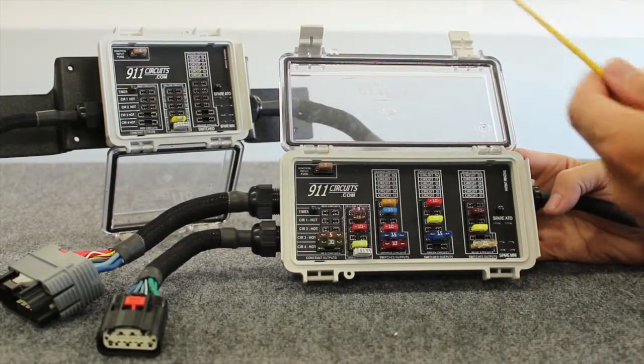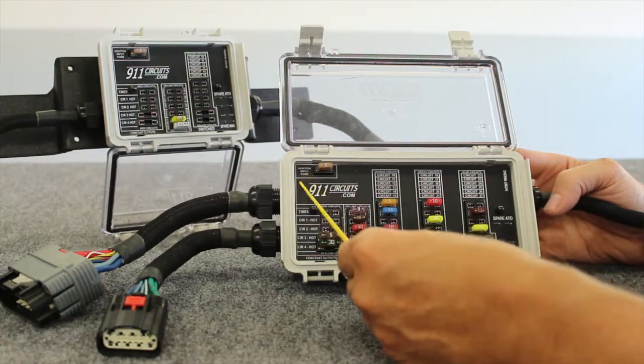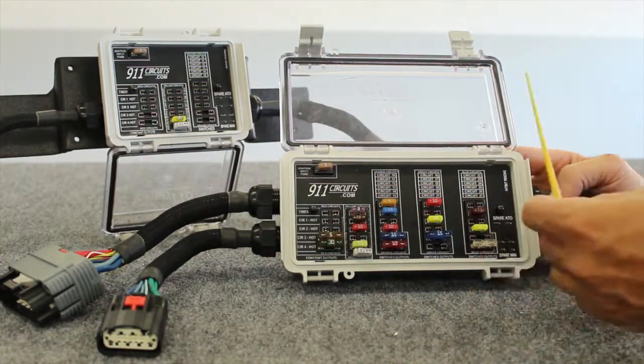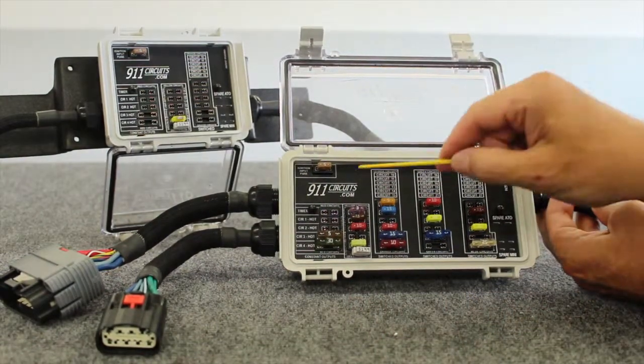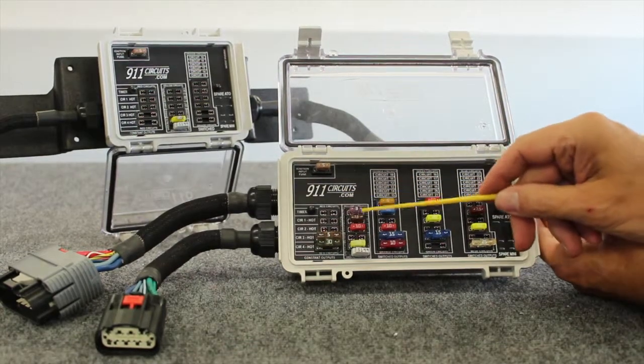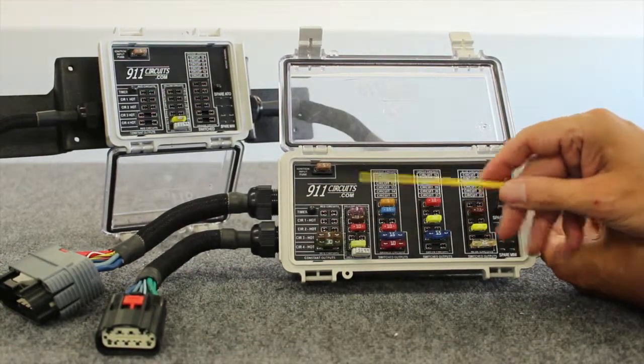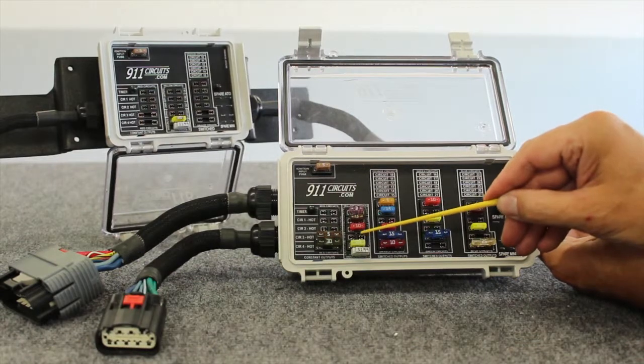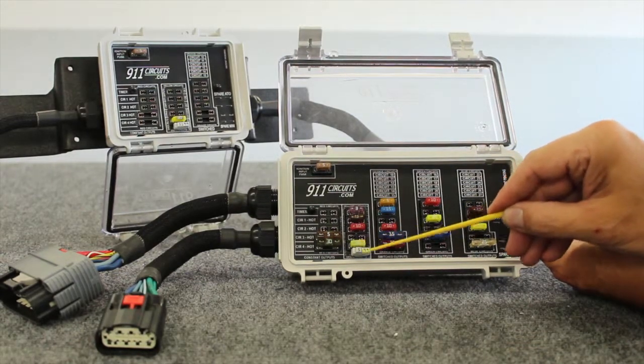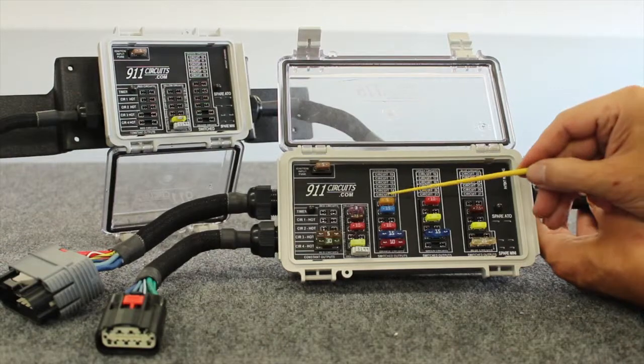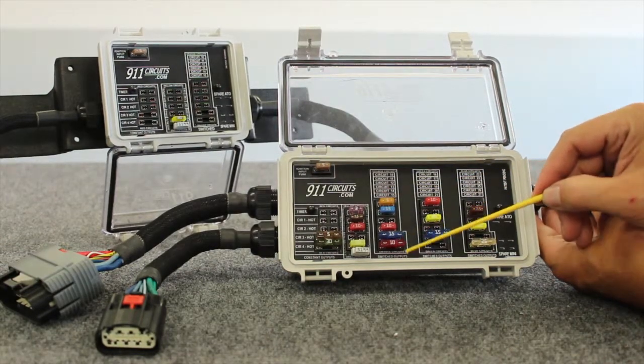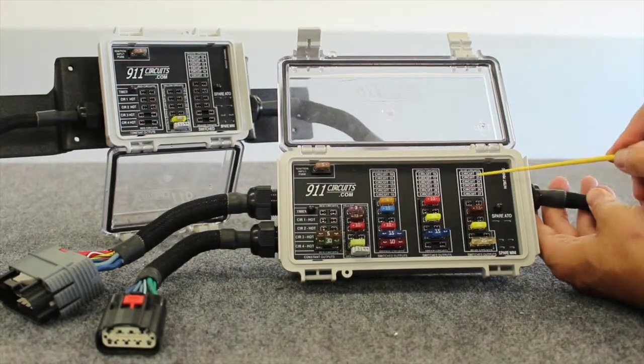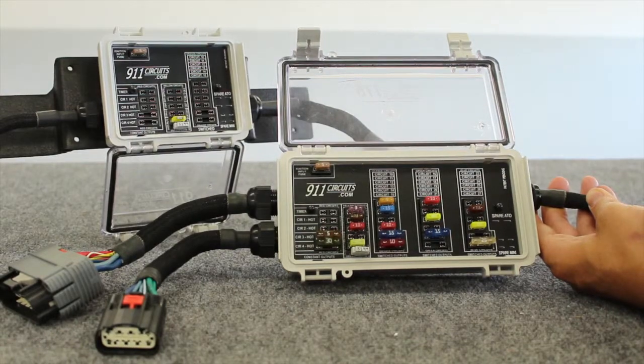So the CH-27 is functionally identical to the CH-15 on this part of the board. So you still have your initial ones that are hot. Your next three, again, are light-duty, hot. This is your bypass. This is your siren speaker. This is a mute again for the siren speaker. And this is your ignition circuit. But now what we've added is two more ignition circuits for a total output of 27 circuits.